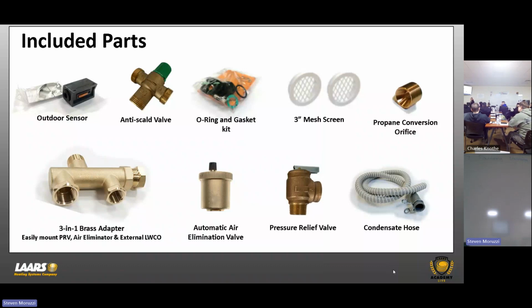Anything you guys want to talk about that I might have missed before we get into error codes and other things? Yes, on condensate. On condensate. If you are not going to be using a condensate hose and you're going to hard pipe it, that's fine and terrific, but make sure you provide a means of vent. So say you're going to use PVC, you'll see that it's going to create an issue because of no vent on the condensate, meaning way to vent the air out of that drain. Okay. And that will hold condensate back to Ken's point, and we will trip that condensate pressure switch.